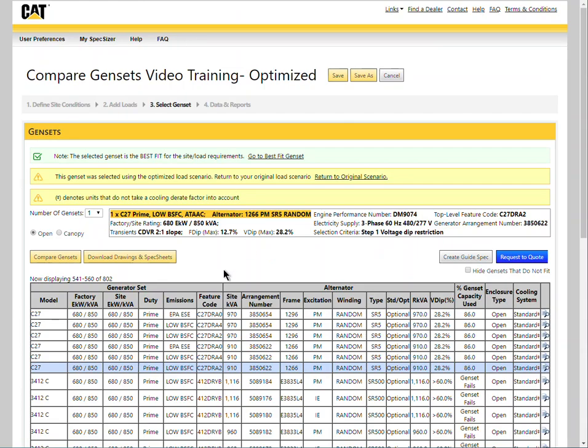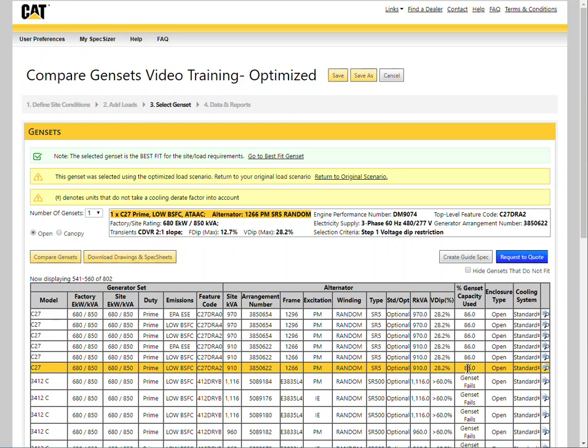The optimized generator set is a C27 with a 1266 frame alternator at 86% capacity used. Not only is the generator frame smaller but the engine size has been reduced from a 69 liter 3516 down to a 27 liter engine. This significantly impacts the generator set overall footprint.